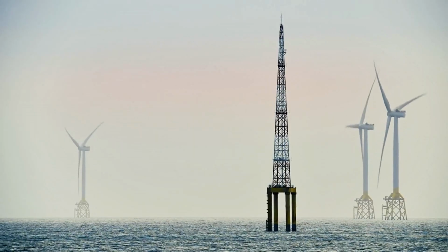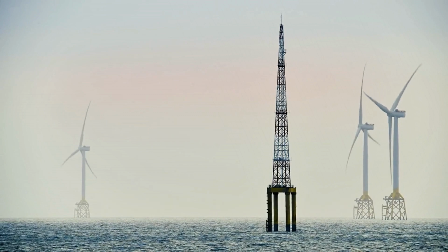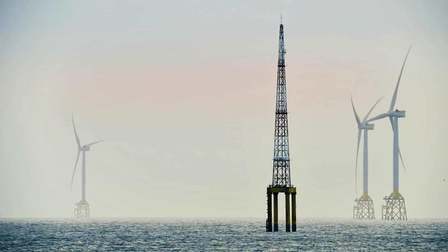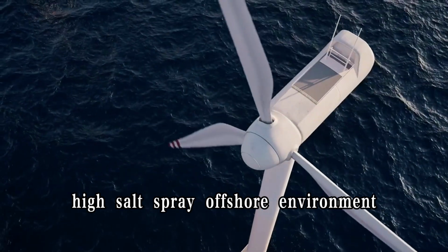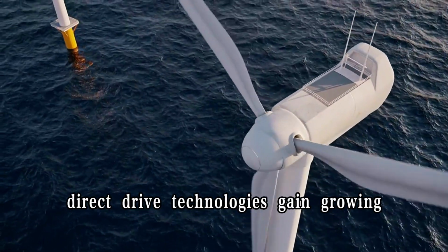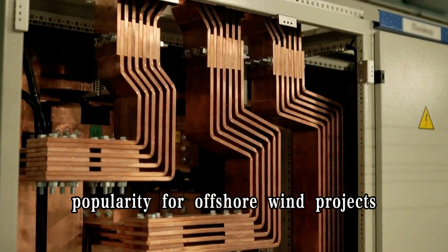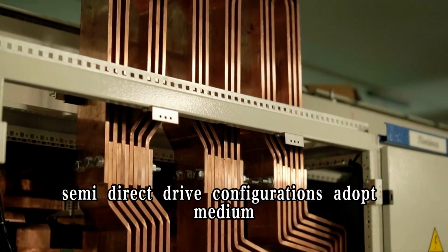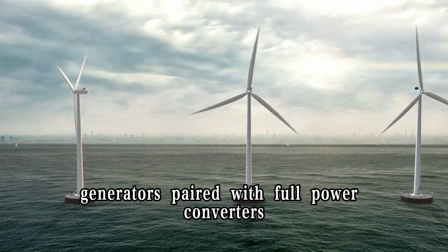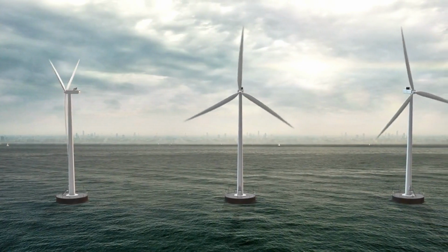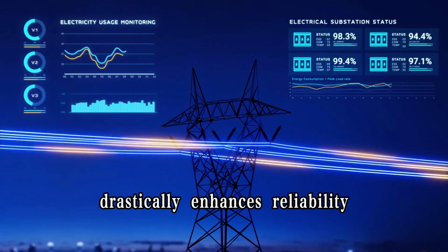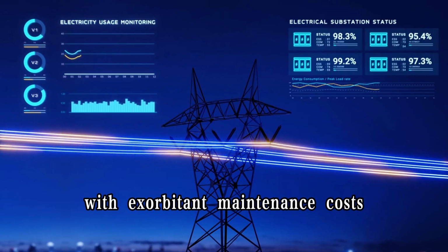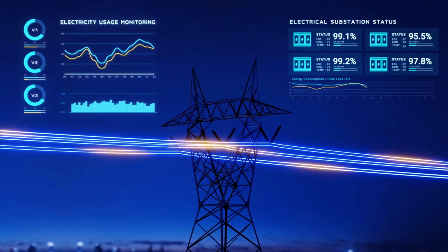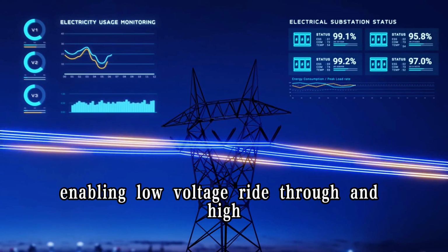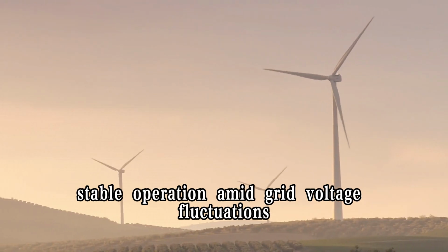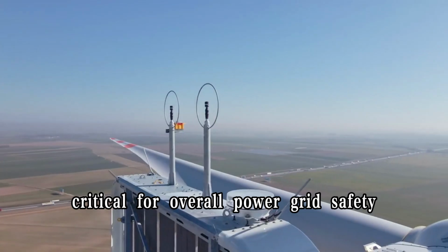Nevertheless, it has an inherent flaw. Slip rings and carbon brushes rely on physical-mechanical contact, suffering gradual wear that requires regular replacement. Corrosion worsens drastically in the high salt spray offshore environment, explaining why semi-direct drive and direct drive technologies gain growing popularity for offshore wind projects. Semi-direct drive configurations adopt medium-speed permanent magnet synchronous generators paired with full power converters. While converter costs rise accordingly, the removal of slip rings and brushes drastically enhances reliability, perfectly suited for offshore sites with exorbitant maintenance costs. Full power converters also deliver superior grid adaptability, enabling low-voltage ride-through and high-voltage ride-through capabilities to sustain stable operation amid grid voltage fluctuations, critical for overall power grid safety.